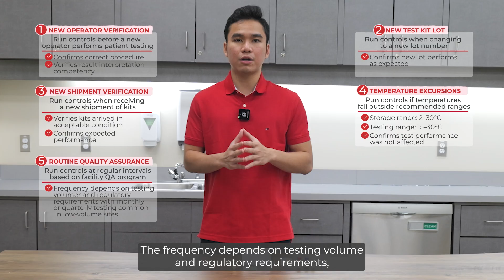Fourth, run controls if storage or testing temperatures fall outside of the recommended temperature ranges of 2 to 30 degrees Celsius for storage or 15 to 30 degrees Celsius for testing. Temperature excursions may affect the test components, and controls verify whether performance has been affected. Fifth, run controls at regular intervals as determined by the facility's quality assurance program. The frequency depends on testing volume and regulatory requirements, with monthly or quarterly testing common in low-volume sites.